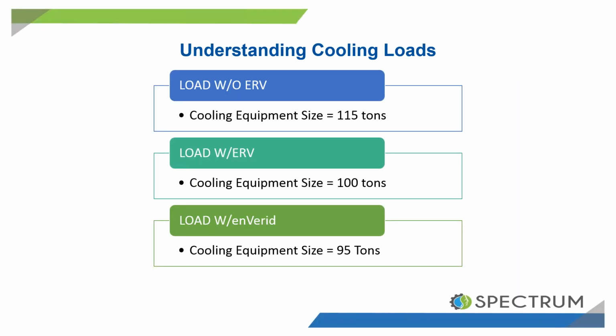And I mentioned before cooling load reduction. So this is again a spectrum reference in terms of how much load reduction can be achieved with EnVerid. It's about 20 ton reduction versus a standard system without an ERV, and about another 5 ton push versus load with an ERV. So fantastic, another point of reference here that we are going to be able to increase the amount of reduction of cooling equipment size versus energy recovery.